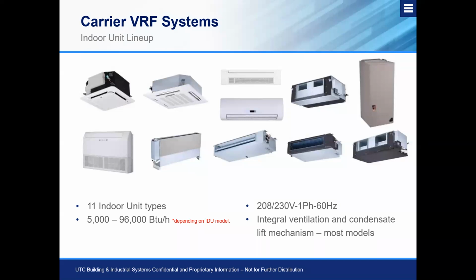And then the outside air unit, of course, can handle the rest, bring it up to a neutral air temperature and be pumped into the space, all part of the VRF system. And of course, this would be for applications where maybe we cannot facilitate a dedicated outside air, or a DOAS unit. Certainly an option that we have and something to consider.